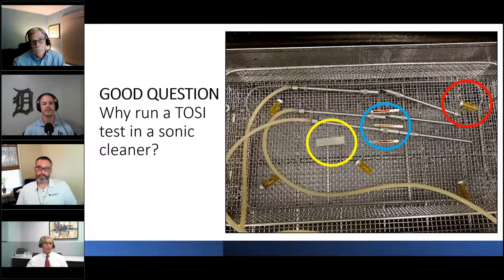So yes, the cavitation was there. Yes, the TOSI or external soil was being removed, which is great. But again, you go back to our good answer, which is running each test that makes sense for the function we want to do. We want to run all the necessary tests of our ultrasonic. In this particular case, external soil removal passed, cavitation or ultrasonic energy test passed, but we did not pass the lumen or internal soil removal test. And therefore we were able to find an answer to the problem and solve it.